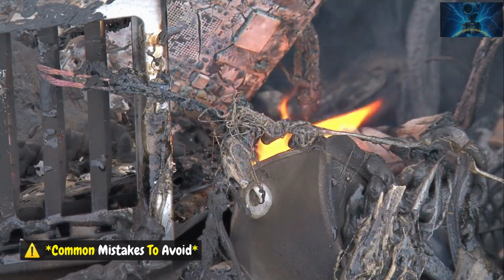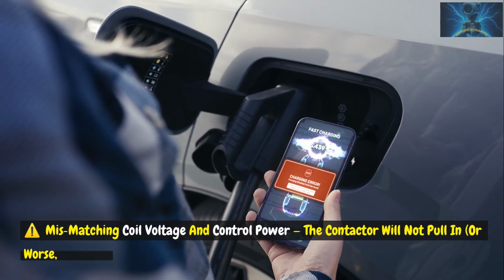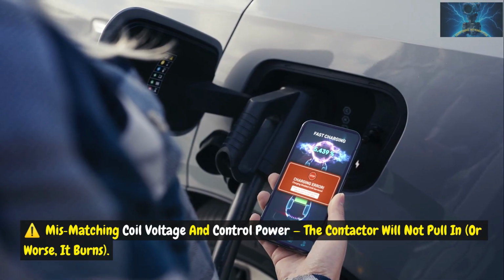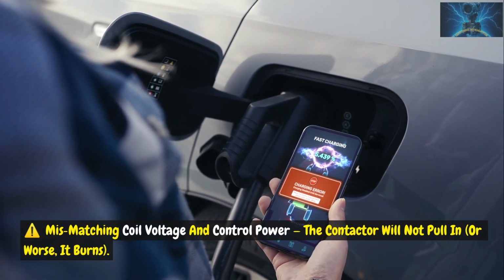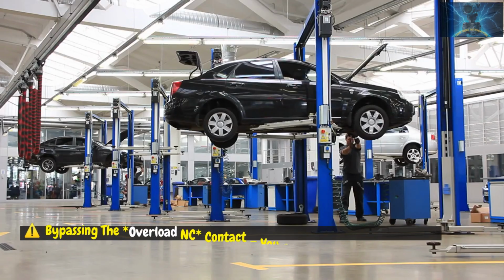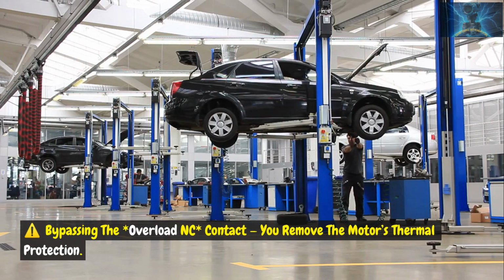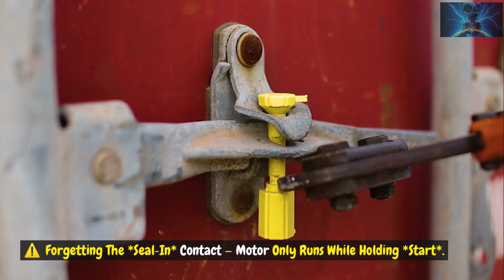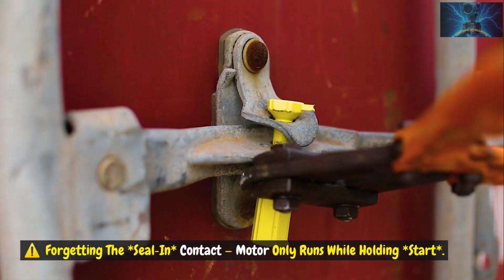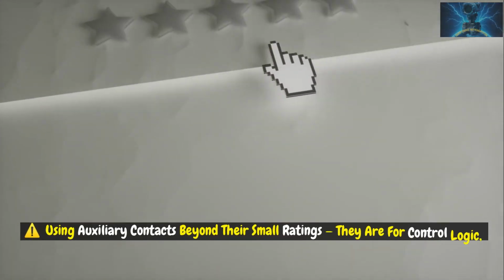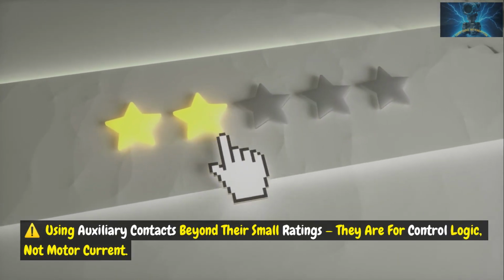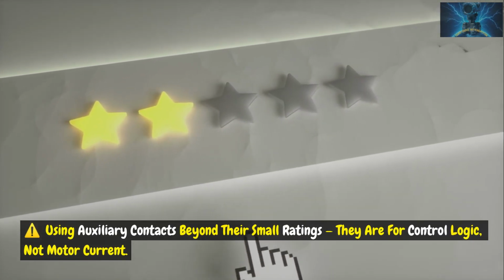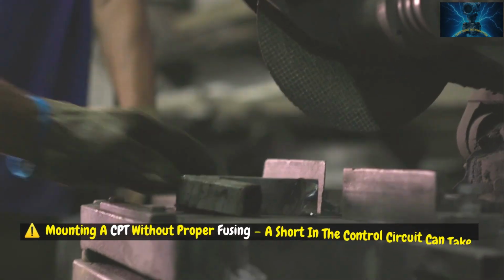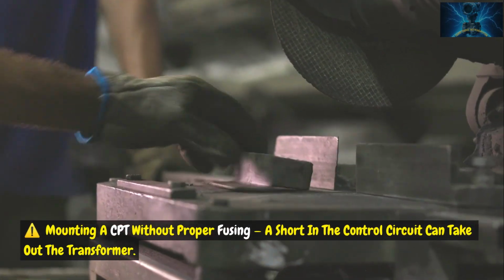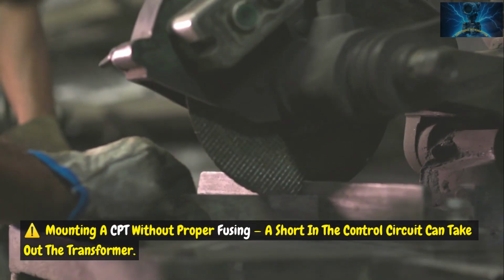Common mistakes to avoid: mismatching coil voltage and control power. The contactor will not pull in, or worse, it burns. Bypassing the overload NC contact, you remove the motor's thermal protection. Forgetting the seal-in contact, the motor only runs while holding start. Using auxiliary contacts beyond their small ratings; they are for control logic, not motor current. Mounting a CPT without proper fusing; a short in the control circuit can take out the transformer.